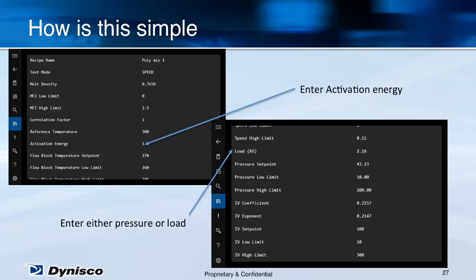You might be saying to yourself that the title of this is Simplified Rheology, but that was a lot of math. On an actual Dynisco indicator, there are a couple of setup screens that will allow you to enter the parameters we discussed utilizing existing terminology that your operators are already familiar with. For instance, you can set up the pressure control value by simply entering the test load from your laboratory melt flow index test. We have simple methods to determine each of the parameters, and we can walk you through the process as you set up your system.